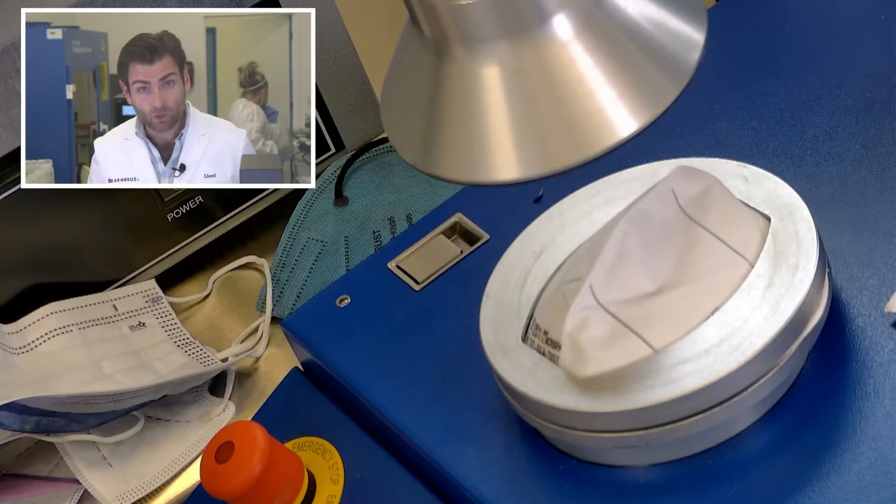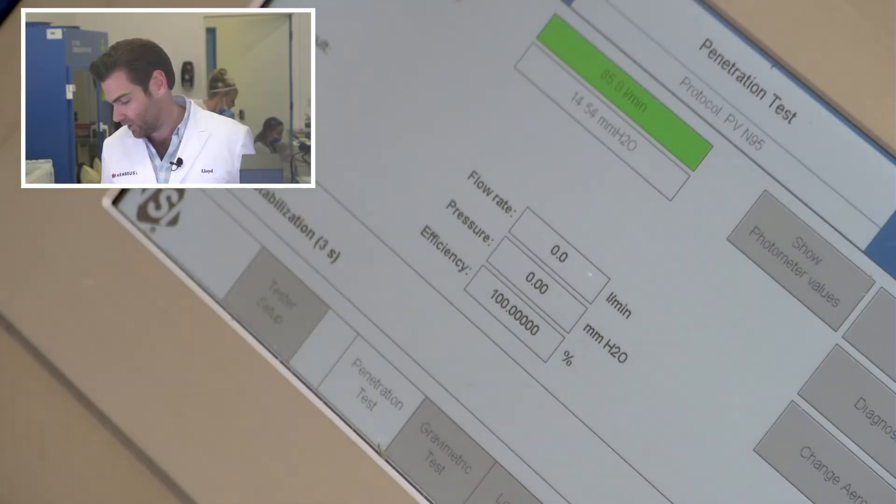That camera — and we're going down. All right, and we're letting her rip. I don't even get to let her rip anymore because the TSI machine automatically does it. All right guys, this is a PFE machine. We're doing the NIOSH N95 PFE particulate filtration efficiency test here. This is the same test, the same model of machine that the CDC uses to test masks. They tested this mask before and got 99%. I expect to get something similar.